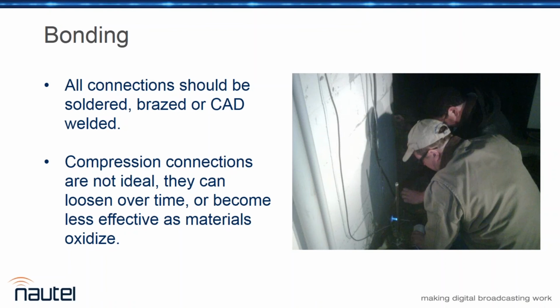By the same token, a lot of times you'll walk into a site and see two pieces of strap joined together by folding them over a couple of times, hammering them flat, and driving a screw through them into the floor. The issue is that the surface of the copper oxidizes because, again, you didn't displace all the air—you can't. Unless it's coated with no-ox, which can help, over time it becomes less effective because it becomes resistive.